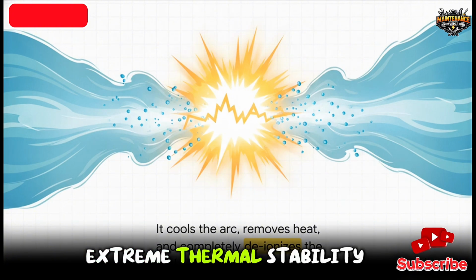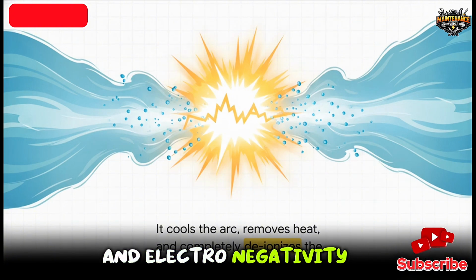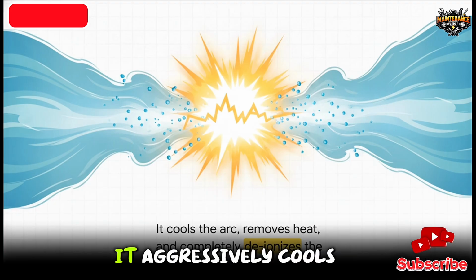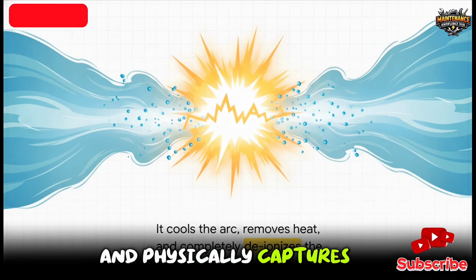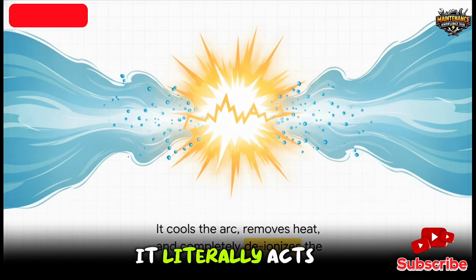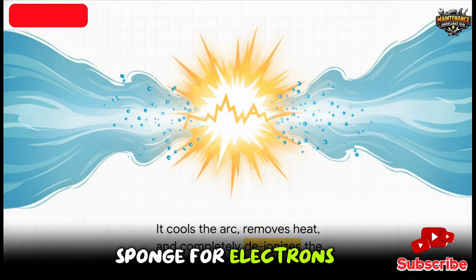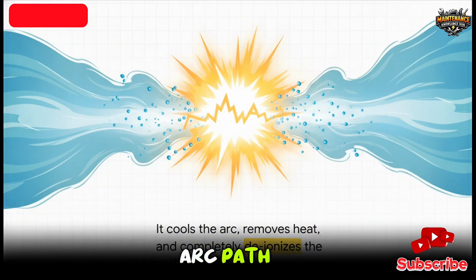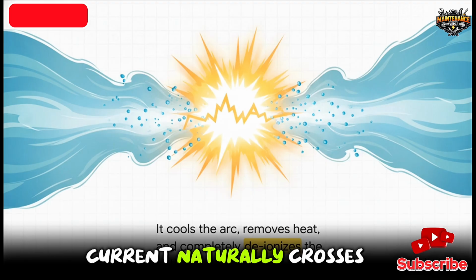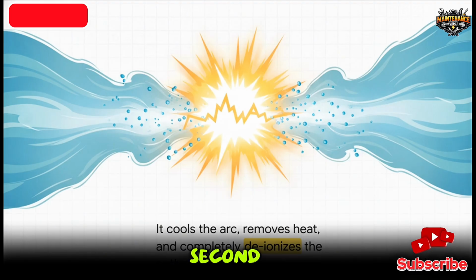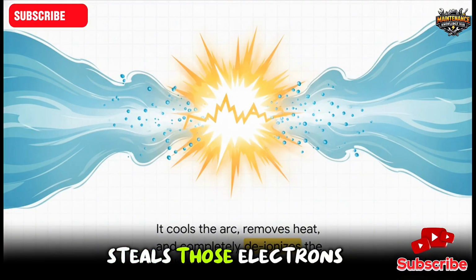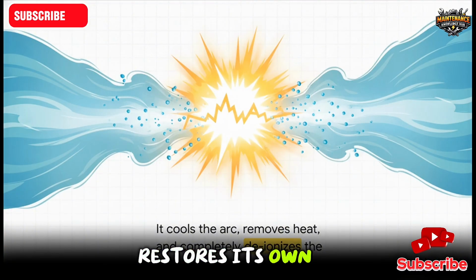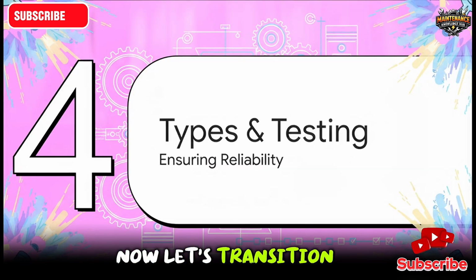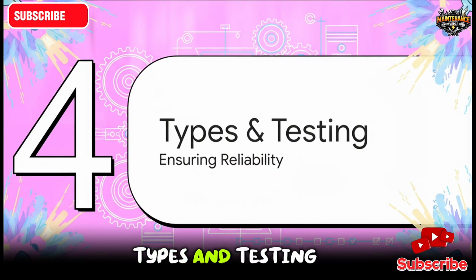SF₆ has extreme thermal stability and electronegativity, so as it blasts across the arc, it aggressively cools it and physically captures the free electrons. It literally acts like a molecular sponge for electrons, completely deionizing the arc path. Now, because alternating current naturally crosses 0 volts dozens of times a second, the SF₆ gas swoops in at the very next zero crossing, steals those electrons, rapidly restores its own insulating strength, and just kills the arc permanently. Gone.